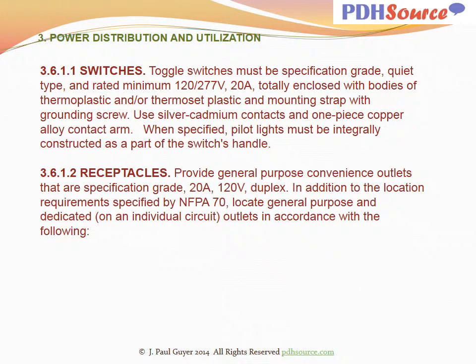Toggle switches must be specification grade, quiet type, and rated minimum 120-277 volt 20 amp, totally enclosed with bodies of thermoplastic and/or thermoset plastic and mounting strap with grounding screw. Use silver cadmium contacts and one piece copper alloy contact arm. When specified, pilot lights must be integrally constructed as a part of the switch's handle.